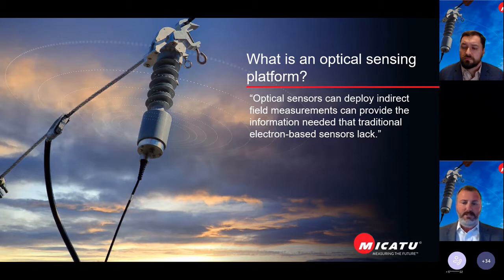They don't pass electrons - rather they measure the electric field using light through those two methods, passing through an optical crystal, which removes all the safety risks associated with legacy instrument technology like transformers, which can become an open circuit, harm people, blow up, catch fire, and aren't safe to work with.